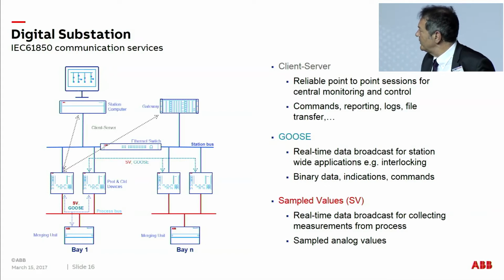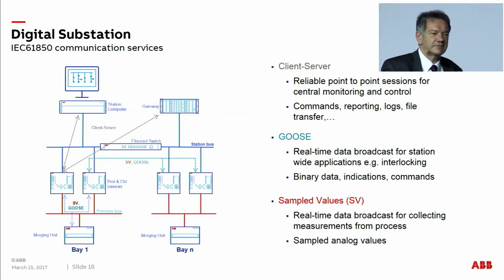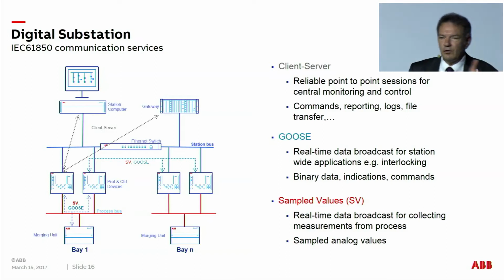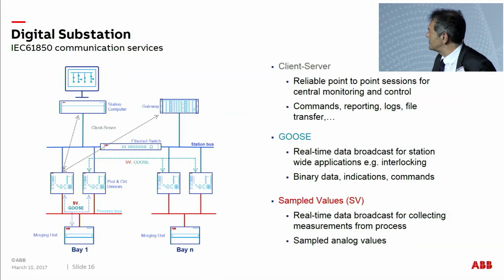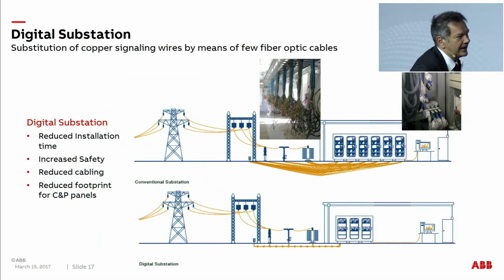What is now new with the process bus, this red stripe down here, is that it can also transmit very accurately so-called sampled values. With 4,000 hertz, all the current and voltage sensors in the substation are measured, 4 kilohertz, and in the future even more. These sampled values are then exchanged between the primary equipment, through merging units, and control and protection. So these are the changes, and this illustrates why this happens.